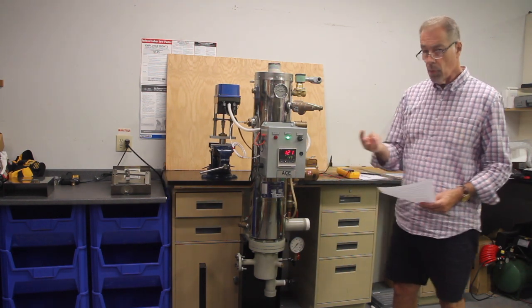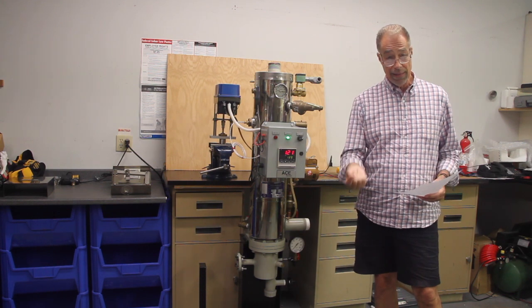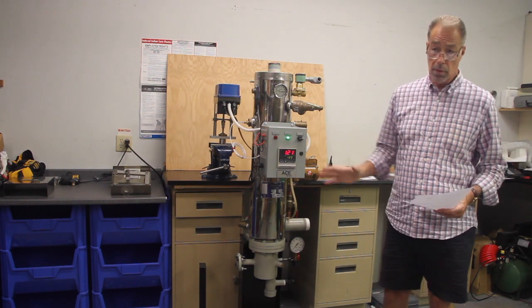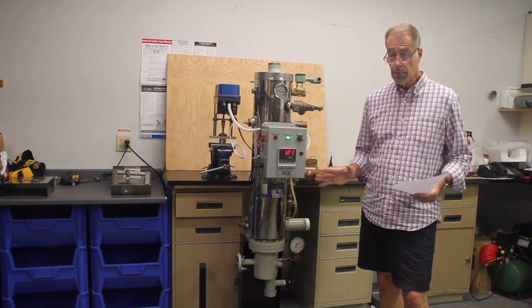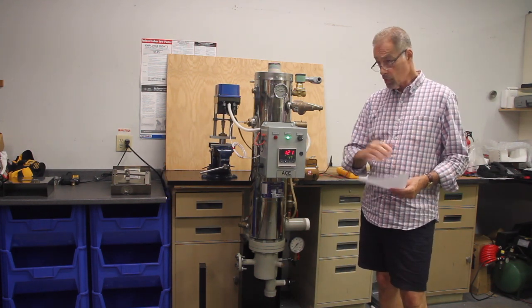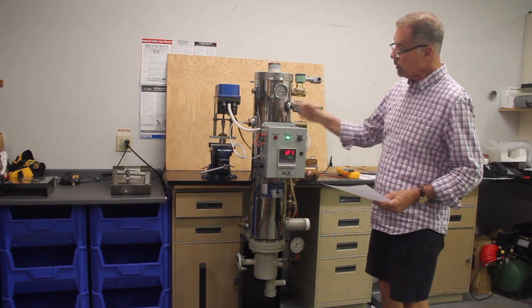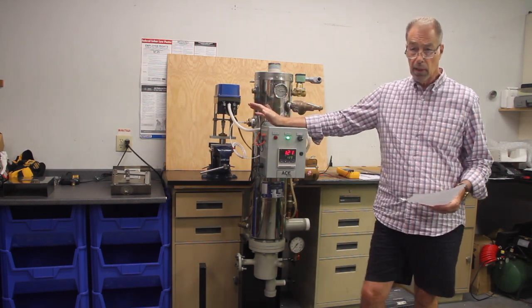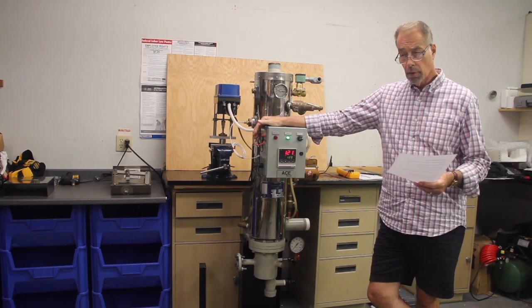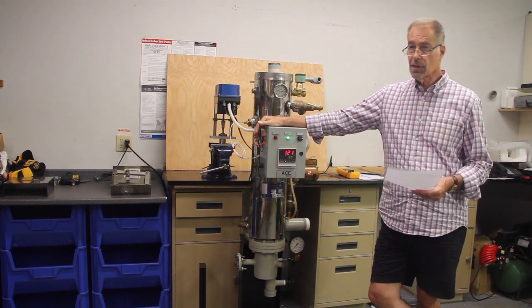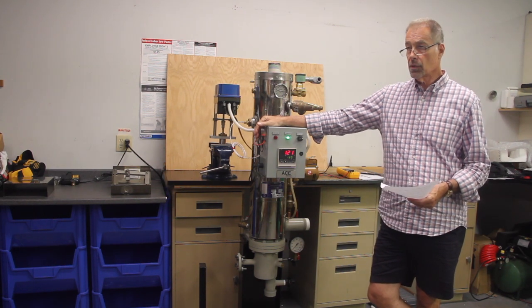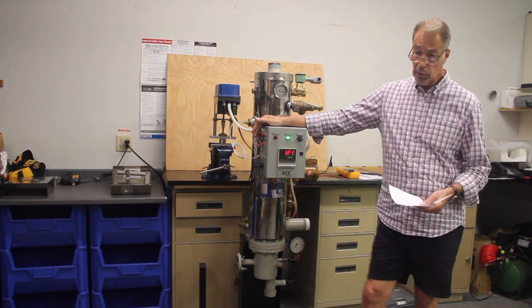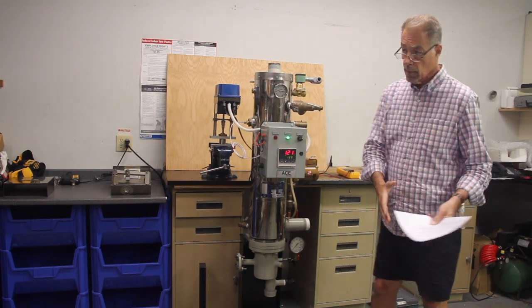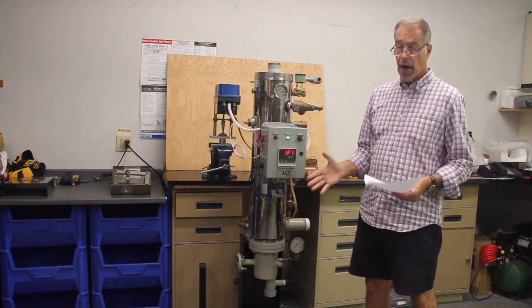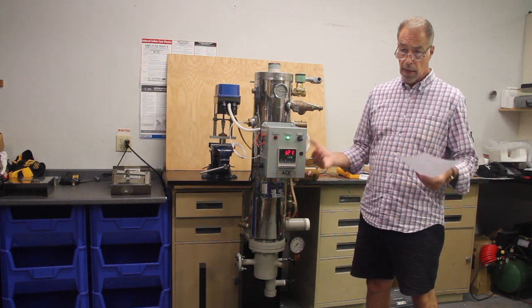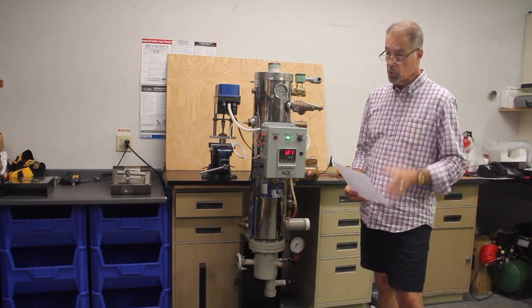So there are 3 ways we can control temperature. We can do it with a steam piloted device, which is a 150-year-old concept, works fine. We can do it pneumatically, which also works very well, or we can do it electronically, which is what we're defaulting to today, because the other 2 scenarios are fraught with problems. More maintenance, compressor maintenance. Pneumatics are your fastest and probably the most reliable. It's just that you have that compressor to maintain. Steam piloted devices are fine until the pilot fails, and then you've got a problem on your hands troubleshooting.